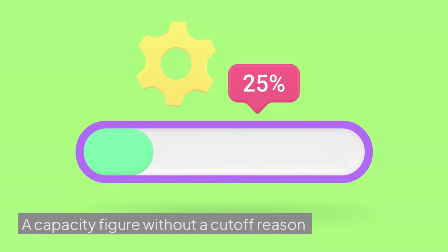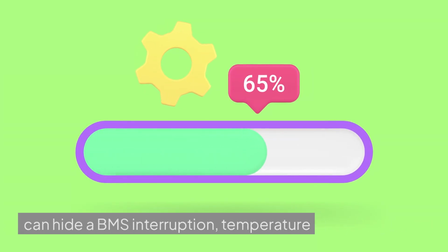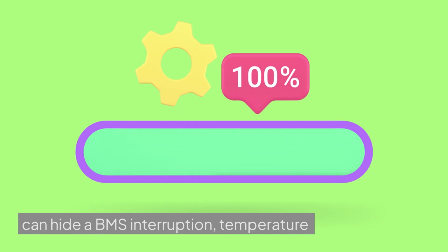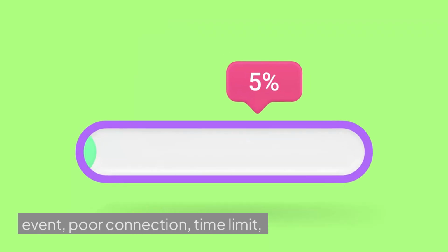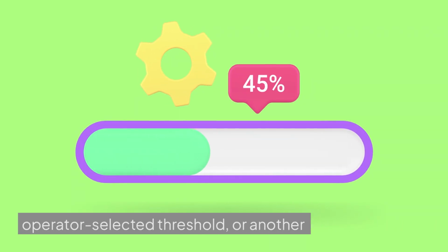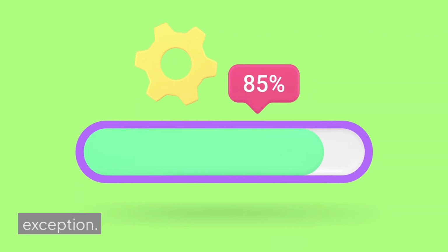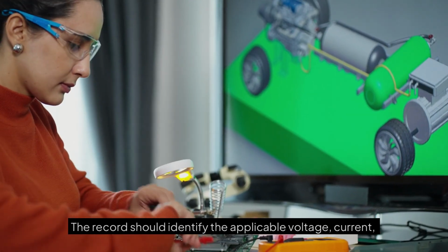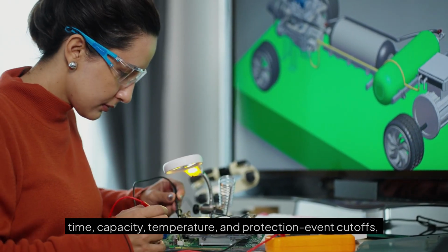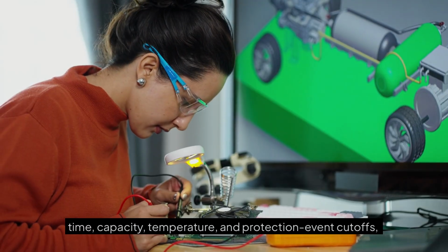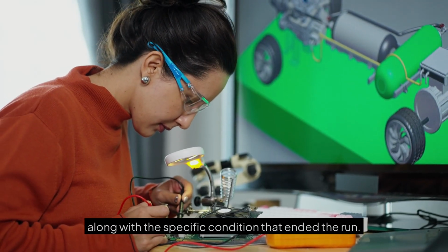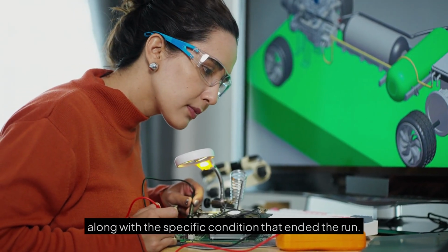A capacity figure without a cutoff reason can hide a BMS interruption, temperature event, poor connection, time limit, operator-selected threshold, or another exception. The record should identify the applicable voltage, current, time, capacity, temperature, and protection event cutoffs, along with the specific condition that ended the run.